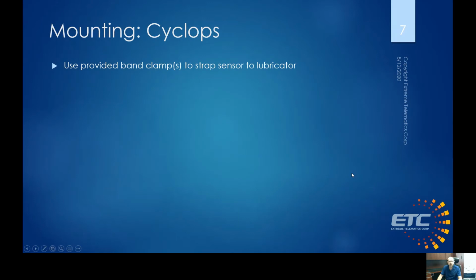All right, so when it comes to mounting, it's a little bit different between the Cyclops and the Sasquatch. So we'll just go over them on two separate slides here. But you use the provided band clamp to strap the sensor to the lubricator. So we provide you a quick release band clamp that can be opened up all the way. You strap it through the built-in legs or around the cable port on the EXP and tighten it against the lubricator. Do make sure that it's tight though and doesn't wiggle, because the sensor's visibility of the Earth's magnetic field will change if the sensor moves. So you want to make sure it's really secure.